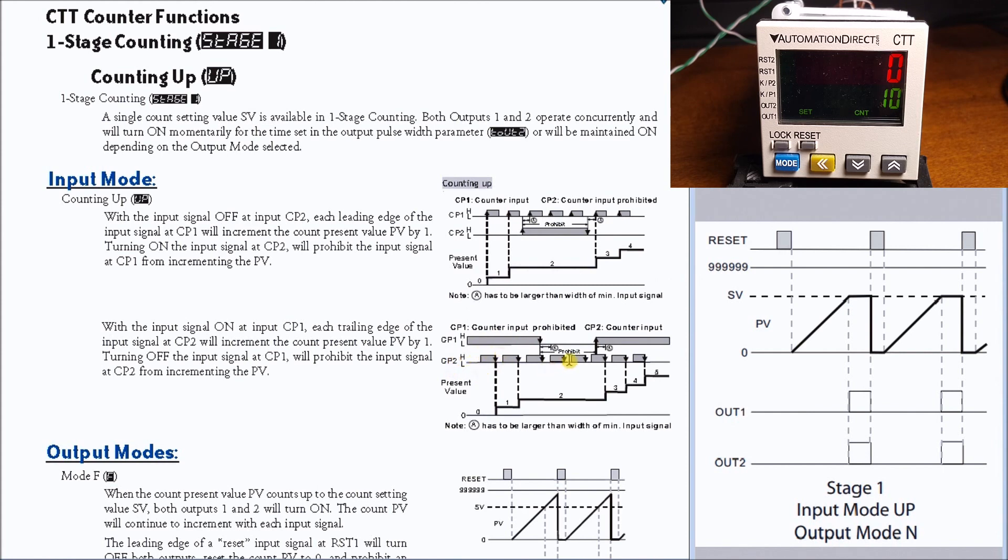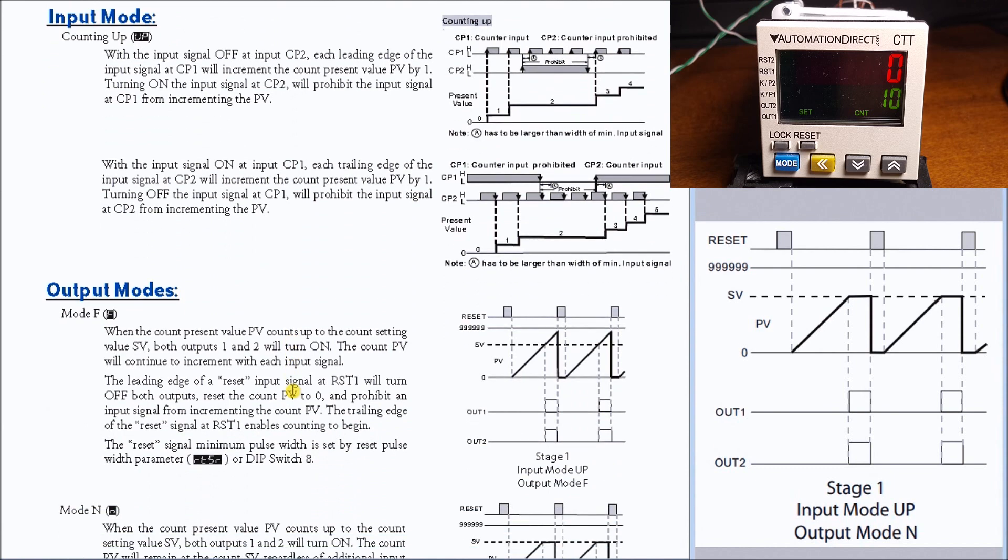That's our up counting. We also have down counting that we can set, which we won't cover here in this example. Basically, stage 1 counting is a single output setting. What happens is both outputs operate at the same time and will turn on momentarily when the set value equals the present value, or be maintained depending on the output mode that you've selected. We have several different output modes that we can choose from.